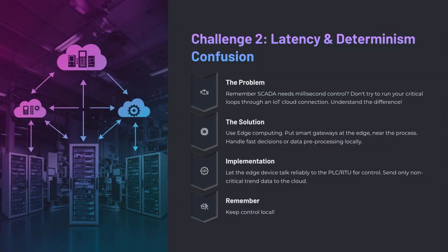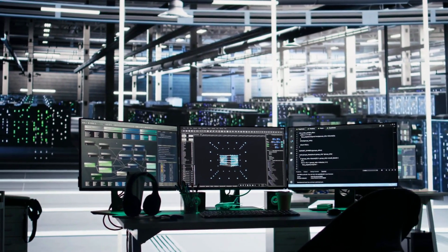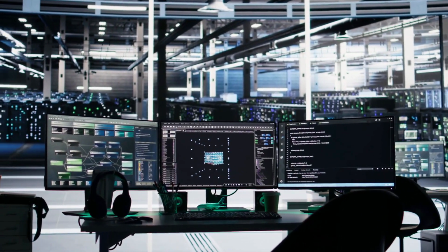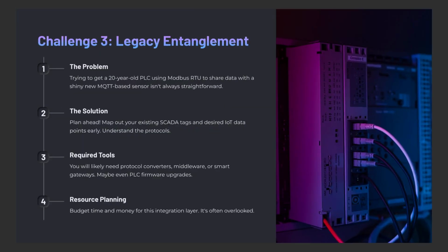Security cannot be an afterthought. Latency, determinism, and confusion. Remember, SCADA needs millisecond control. Don't try to run your critical loops through an IIoT cloud connection. Understand the difference. My advice: use edge computing. Put smart gateways at the edge near the process to handle rapid decisions or data pre-processing. Let the edge device talk reliably to the PLC or RTU for control. Send only the non-critical trend data or summary information up to the cloud for analysis. Keep control local.